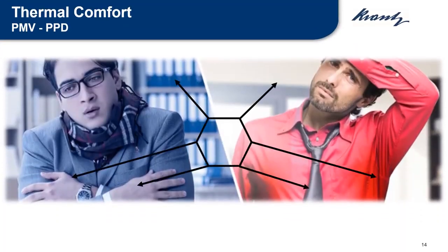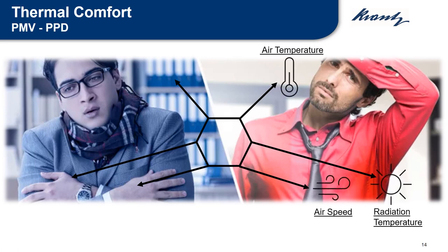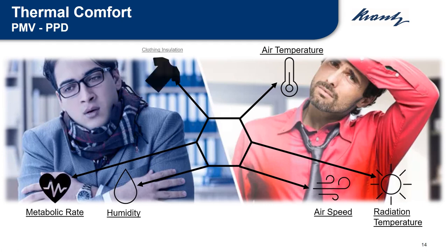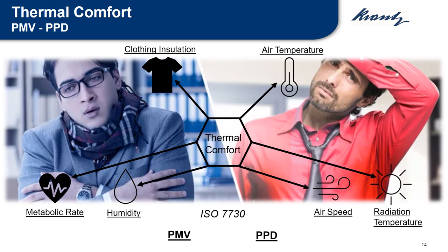The feeling of well-being in an area depends on a number of specific external influencing factors such as indoor air temperature, radiation temperature, air speed and indoor relative humidity, and is defined as the condition of mind that expresses satisfaction with a thermal environment. The international standard ISO 7730 combines all these parameters in two indexes: predicted mean vote (PMV) and predicted percentage of dissatisfied (PPD).